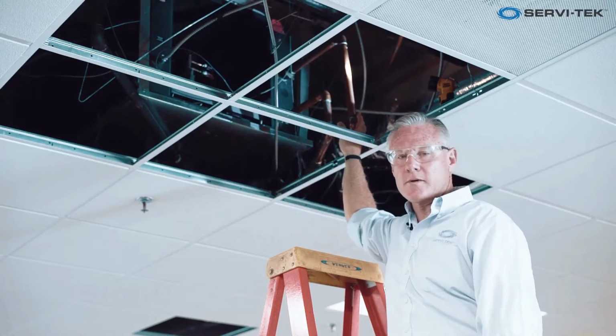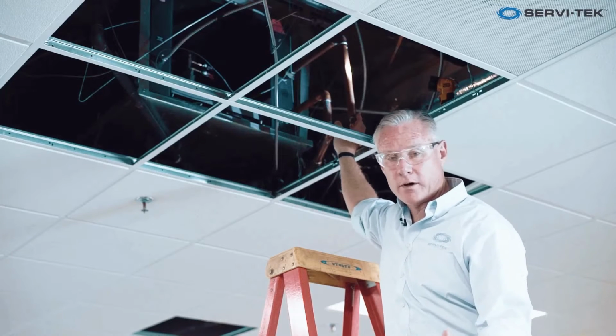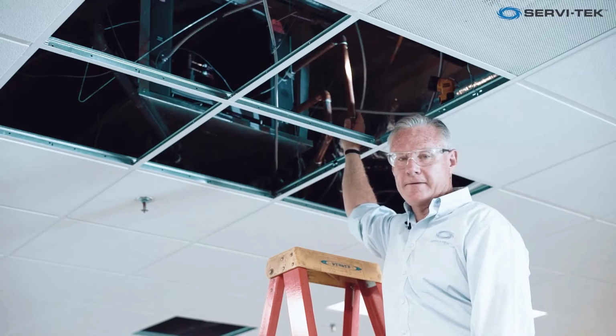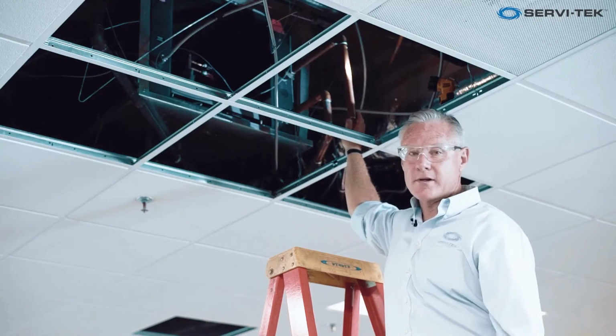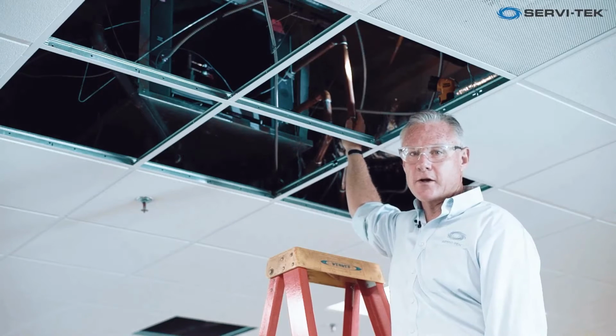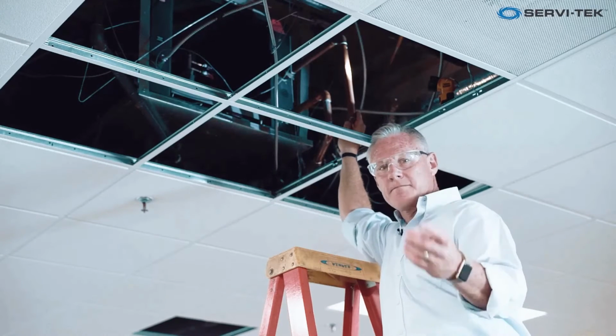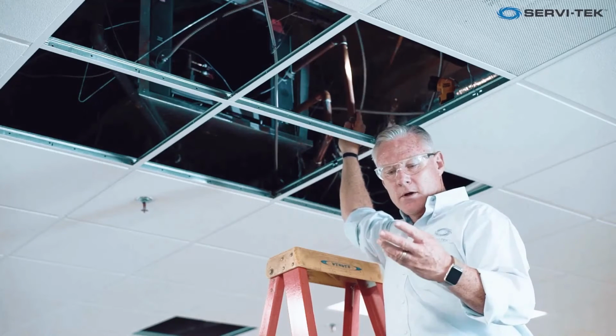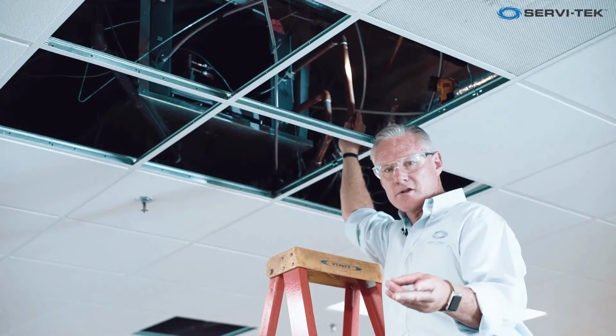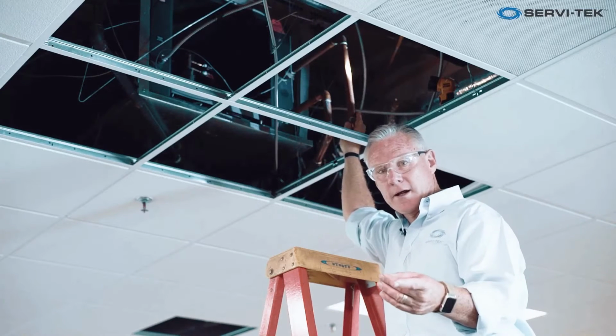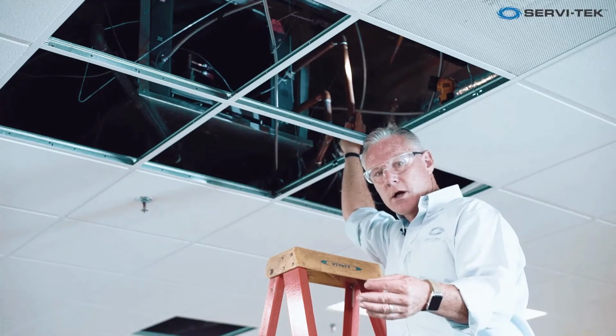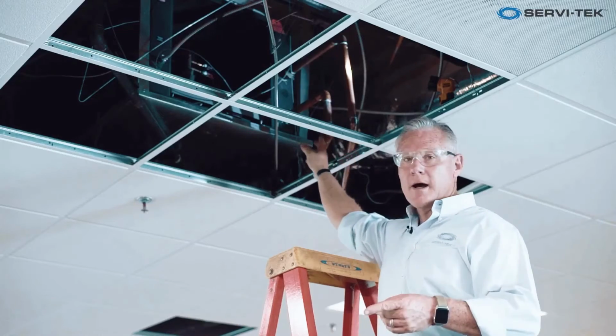That's closed unless you get a leak. There are some component repair issues to these. If they fail, you can actually just change out the compressor without having to change out the entire unit. There's only a few points of connection on a water source heat pump: your condenser water supply, your condenser water return, your electrical connection, your duct work, and then your condensate line.